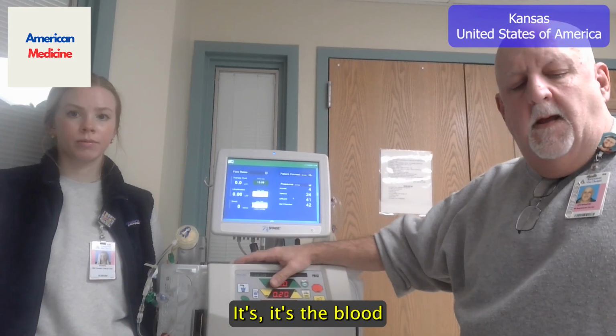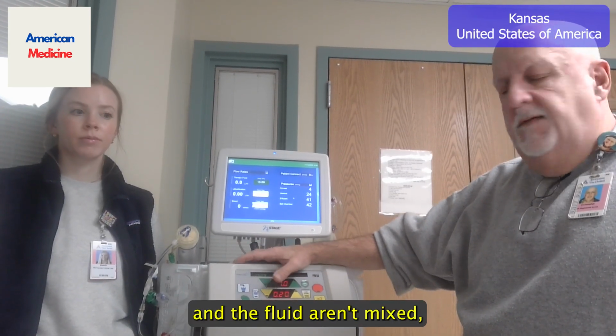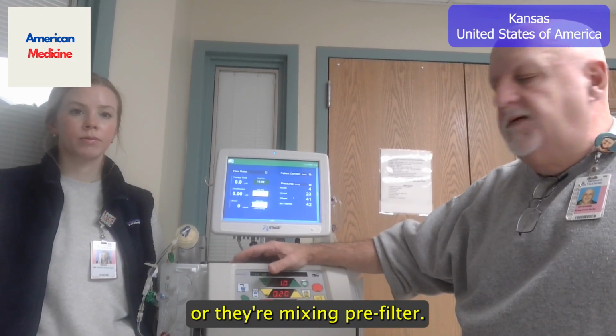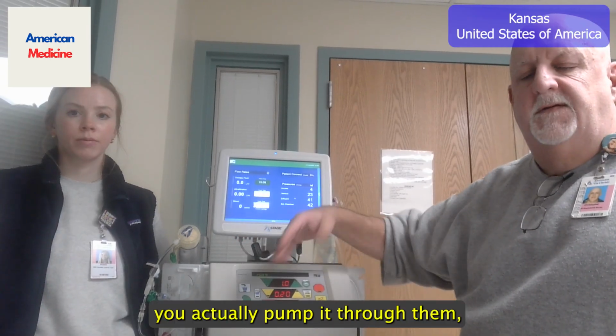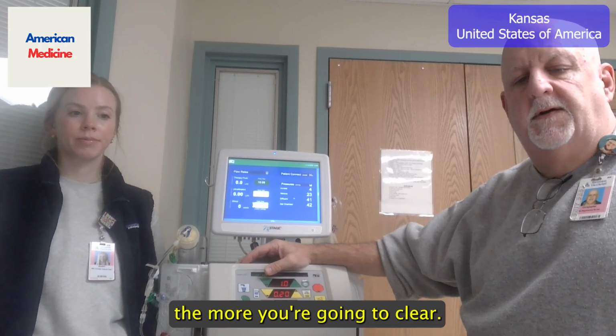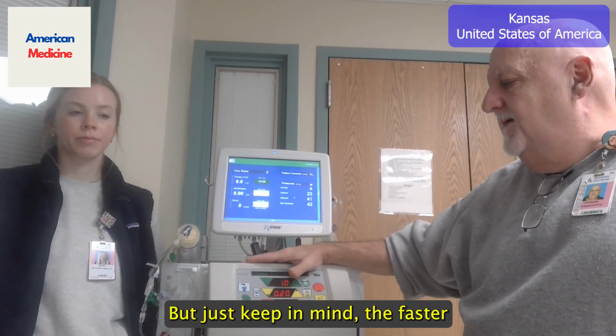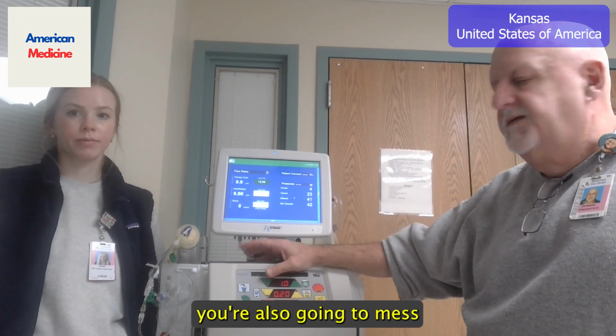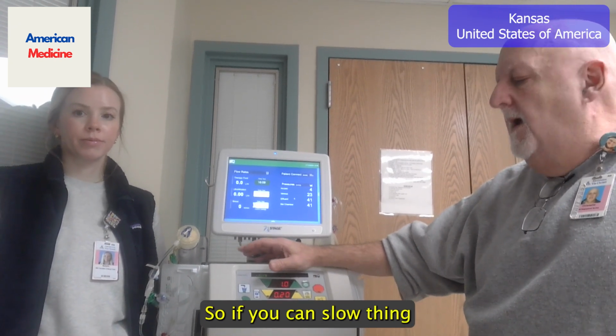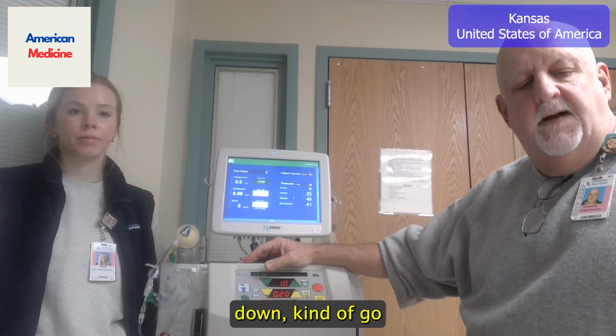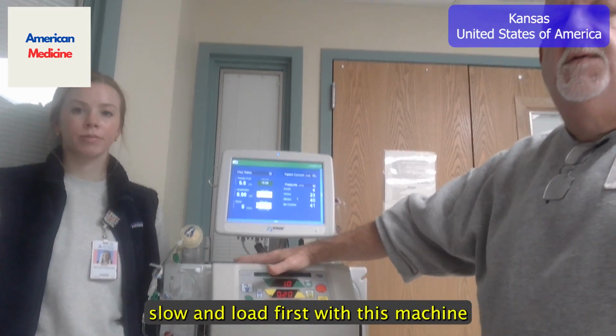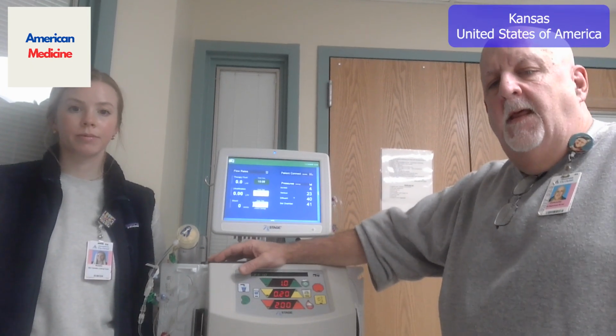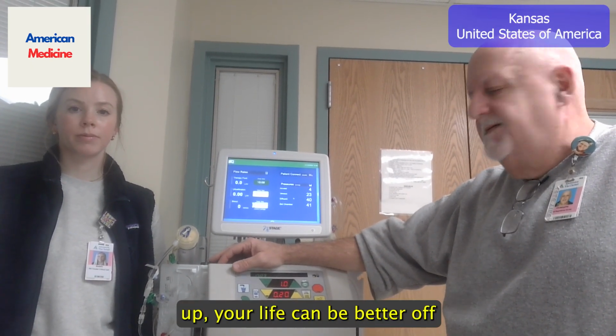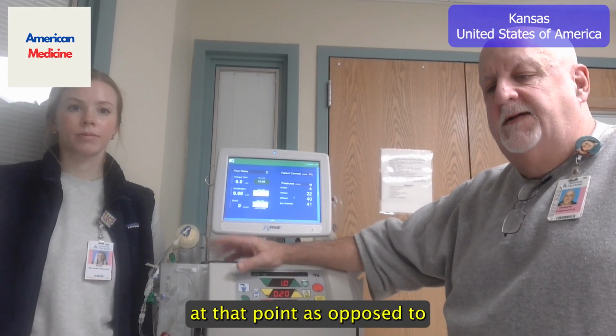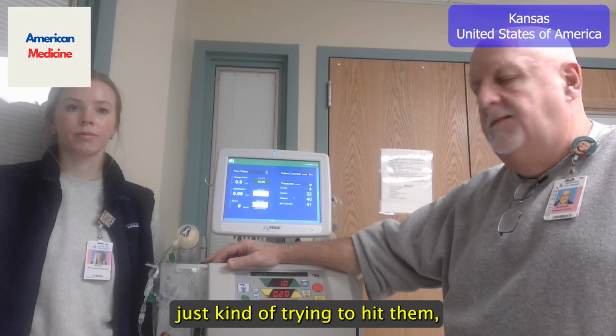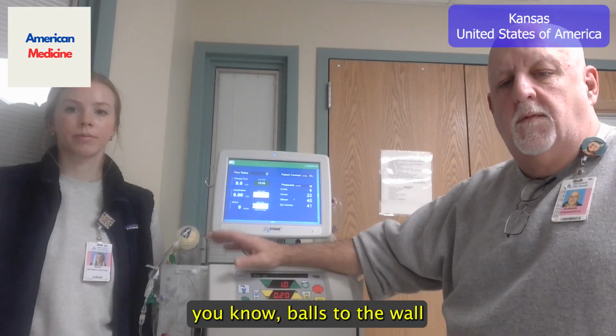It's that the blood and the fluid aren't mixed, or they're mixing pre-filter, and the faster you pump it through, the more you're going to clear. But just keep in mind, the faster you push it through, you're also going to mess with blood pressures. So if you can slow the thing down, go slow and low at first with this machine, and then work your way up, your life's going to be better off, as opposed to just trying to hit them full blast right off the bat.